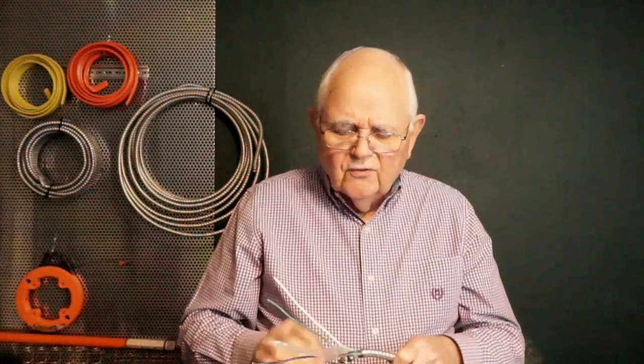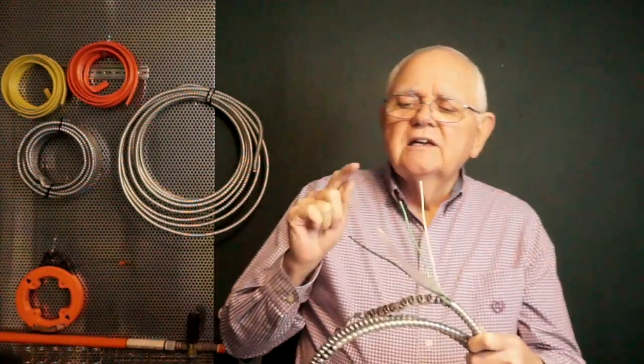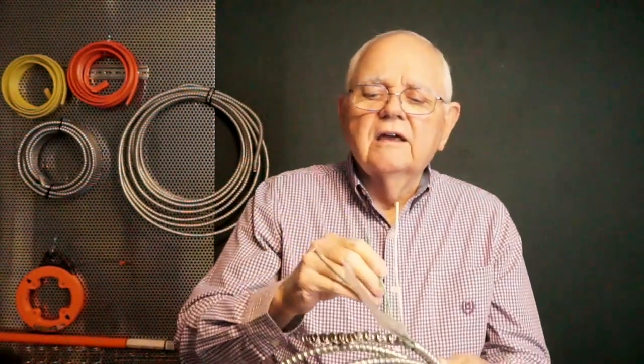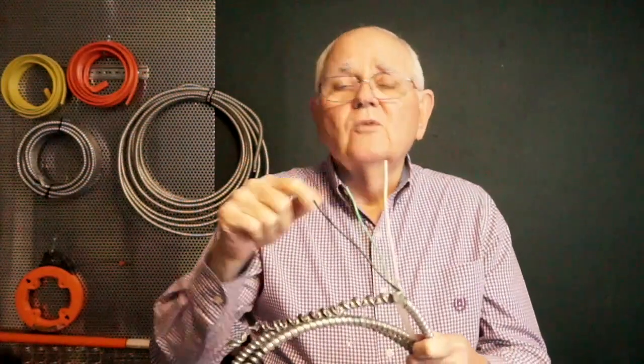And the same is true with the MC cable itself. The UL 1569 standard covers the construction specifications and testing requirements and so forth for MC cable. I can get MC cable. This, for instance, has a number 14 ungrounded conductor, a number 14 grounded conductor, and the 14 AWG equipment grounding conductor, and of course the plastic sheath around it. Now, I can buy it with any combination of conductors I want on the inside. I can get it with an upsized neutral if I need to account for harmonic issues.